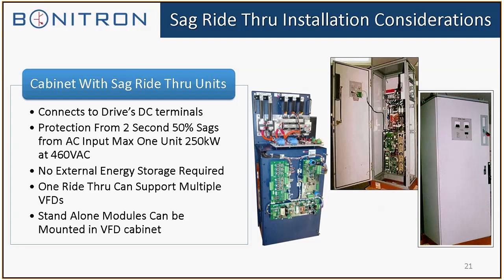So in other words, the standalone modules can be mounted inside the drive cabinet, or the customer can provide their own cabinet as long as they have a disconnect and, you know, the other busware that's required. Or we can provide the full cabinet systems that have the disconnect, that have the DD4 display, everything mounted inside the cabinet. You just connect it to the drive.